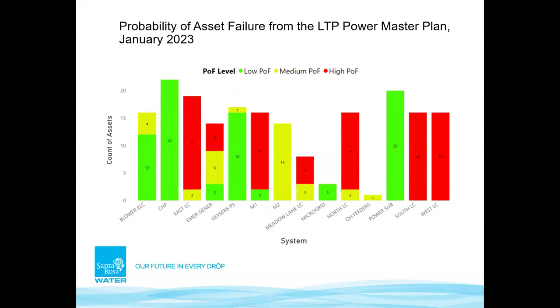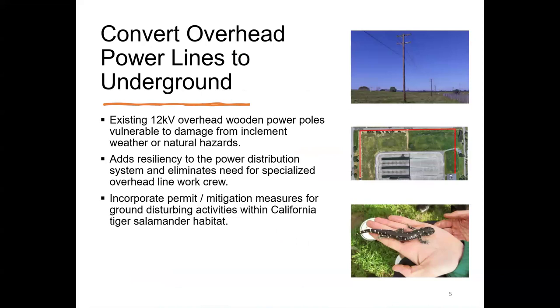There's a picture of the poles — they're leaning and need to be replaced. Having overhead poles means they need to be maintained by specialized crews, kept clean, and they're vulnerable to weather and natural hazards. By undergrounding the overhead feeder lines, those issues are addressed.